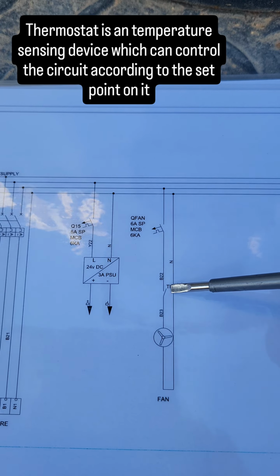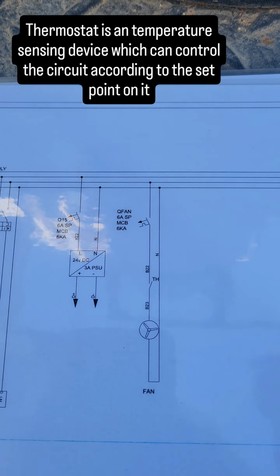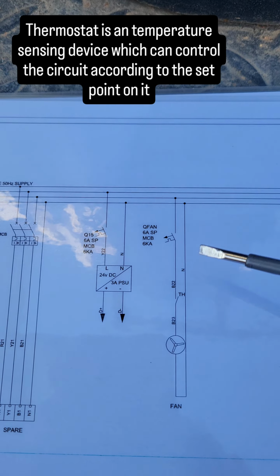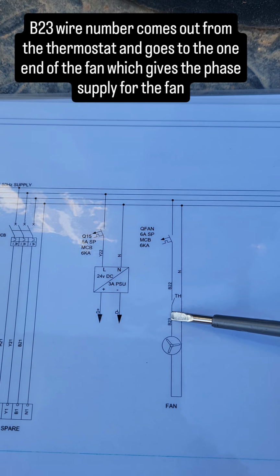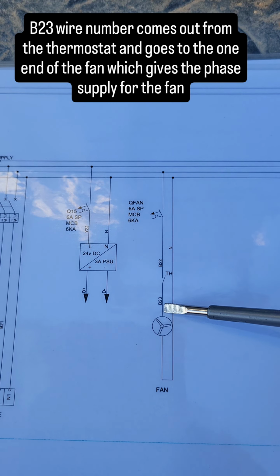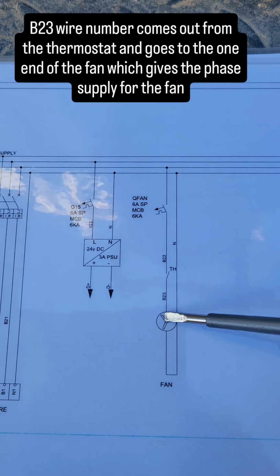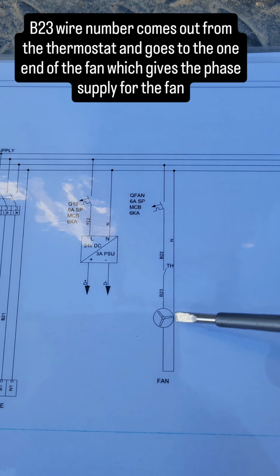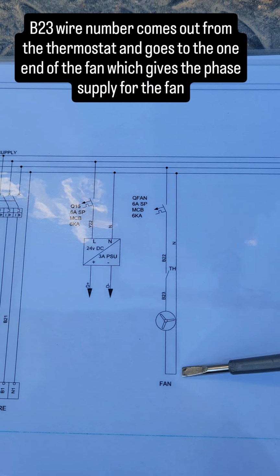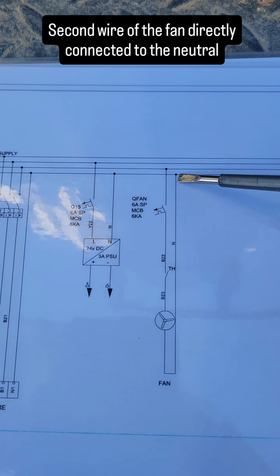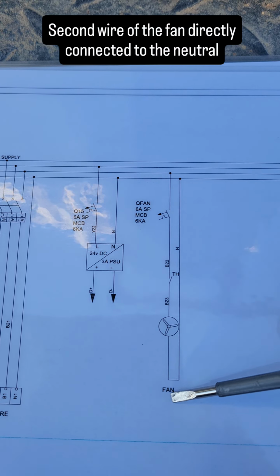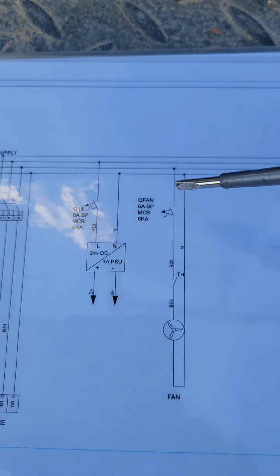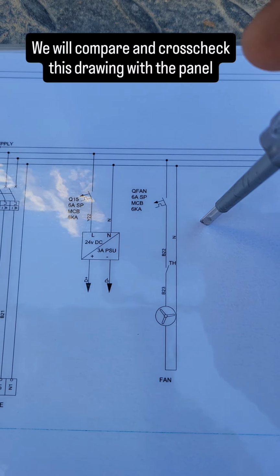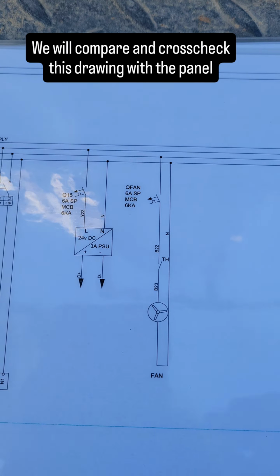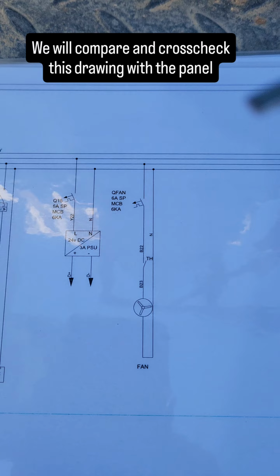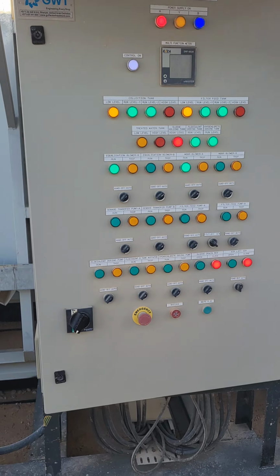Now what is TH? TH is the thermostat, and again from the output of the thermostat, wire number B23 goes to the input of the fan, which gives phase to the fan on one end, and the second end goes directly to the neutral. So this is how the fan gets phase and neutral. Now we will compare this drawing to the panel, and let's see where the components are located inside the panel.